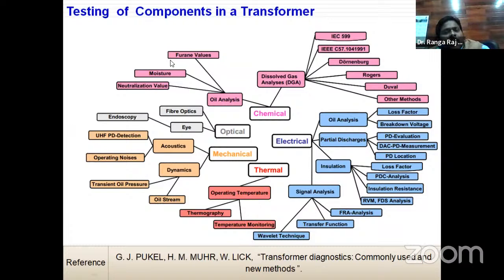Moisture, furan contents, neutralization value - we also know that due to the rise in temperature of the oil, we find so many gases released from the oil at different temperatures. Different gases are released: hydrogen, ethane, methane, acetylene, ethylene, carbon dioxide, carbon monoxide. 5 to 6 gases are released from the oil.